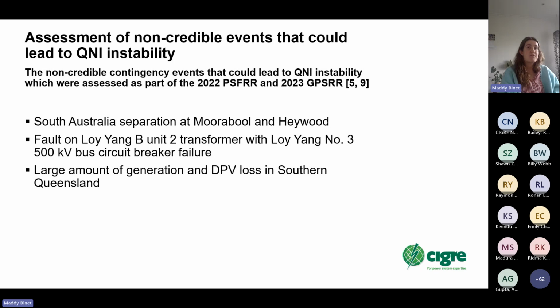We also looked at a fault on the Loy Yang B Unit 2 transformer with a circuit breaker failure. This CB fail event can result in the loss of both Loy Yang B units and also Valley Power - an example of a significant N-2 or CB fail event that can result in a significant amount of generation being lost south of Queensland. Loy Yang is in Victoria, so this is a remote generation contingency event for Queensland export scenarios.